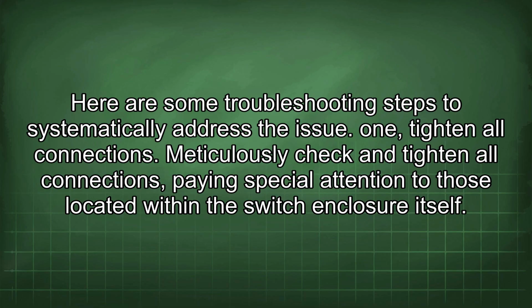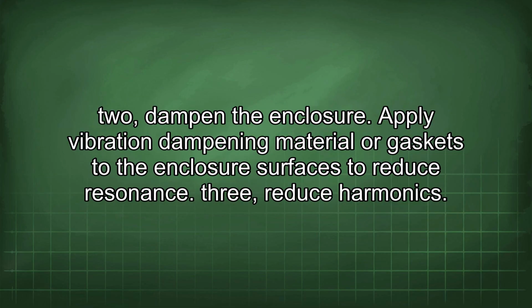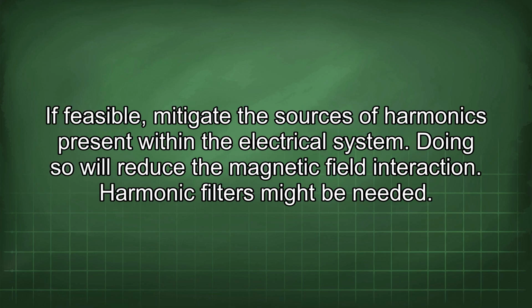1. Tighten all connections. Meticulously check and tighten all connections, paying special attention to those located within the switch enclosure itself. 2. Dampen the enclosure. Apply vibration dampening material or gaskets to the enclosure surfaces to reduce resonance. 3. Reduce harmonics. If feasible, mitigate the sources of harmonics present within the electrical system. Doing so will reduce the magnetic field interaction. Harmonic filters might be needed.